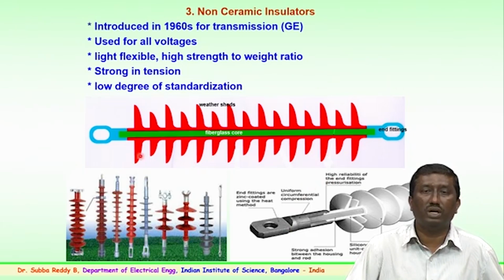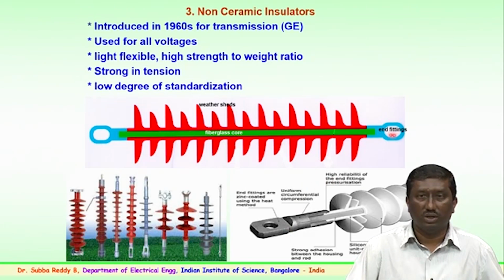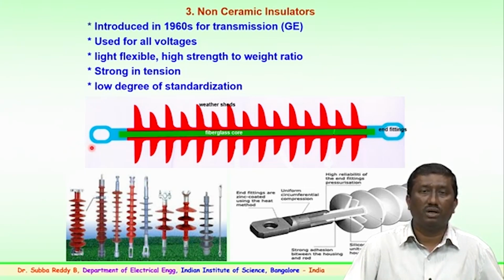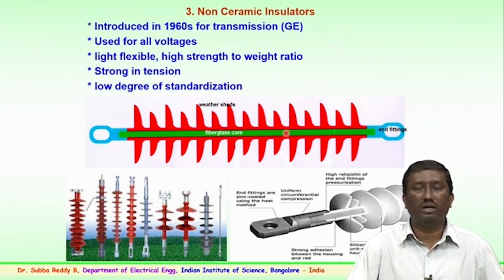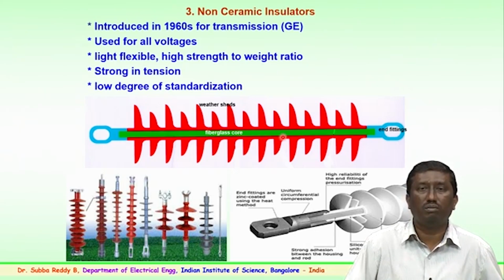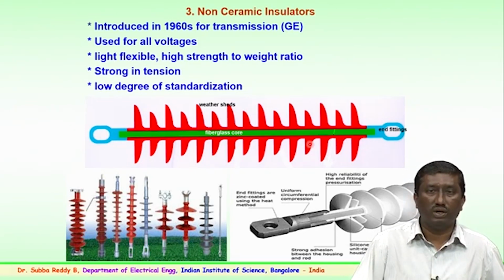standardization. So, this is how a typical polymer insulator looks. A polymer insulator, as I mentioned, will have a fiberglass rod, which is shown here in green color. This fiberglass rod is fixed with the metal end fittings. Of the metal end fittings, one is connected to the tower and the other is connected to the conductors with suitable hardware. Later on, with the help of liquid injection molding, the silicon rubber or polymer sheds, or weathering sheds as we call them, are molded on this fiberglass rod.